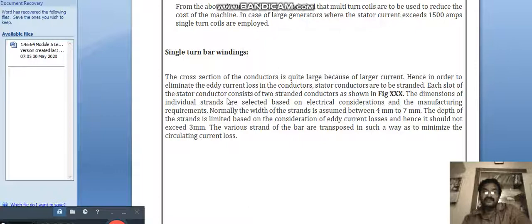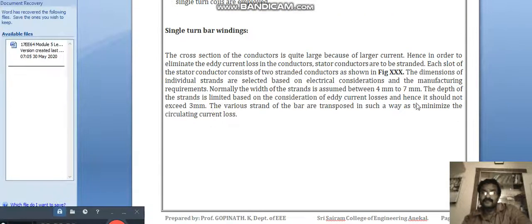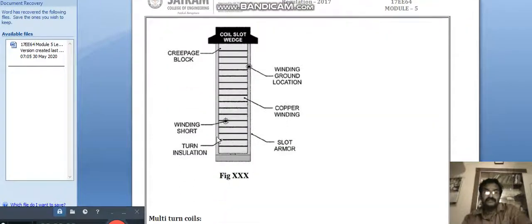Each slot of the stator conductor consists of two stranded conductors as shown in the figure. The dimensions of the individual strands are selected based on electrical considerations and manufacturing requirements. Normally, the width of the strand is assumed between 4 mm to 7 mm. The depth of the strand is limited based on eddy current loss considerations and should not exceed 3 mm. The various strands of the bar are transposed in such a way as to minimize the circulating current loss.